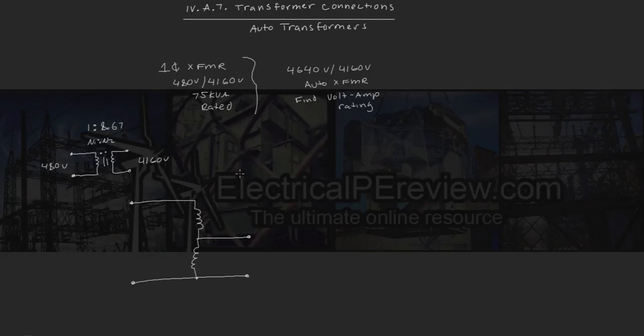So if this is our new connection here, primary winding on top of our secondary winding, here's our common line, here's our new tap for our step down. If this is our input, if we take our 4160 winding on the secondary plus our 480 volt on our primary, we do the math and that gives us 4640 volts. Since we're stepping down to 4160 on the secondary, we know we want to keep this coil as the bottom coil. So this is going to be our output, plus 4160 volts, minus. We know our input is going to be 4640 volts, minus.